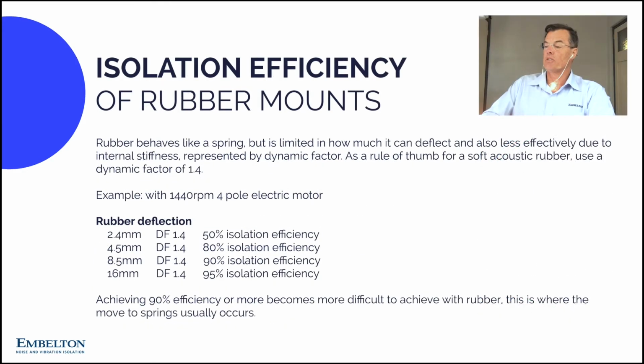Rubber mounts are ideal for non-critical application. It is limited to how far it can be compressed and has an internal stiffness, so it's not exactly acting like a spring. Up to 90% isolation efficiency is available for a 4-pole motor. Over that, or for large machines, is where we move to springs.